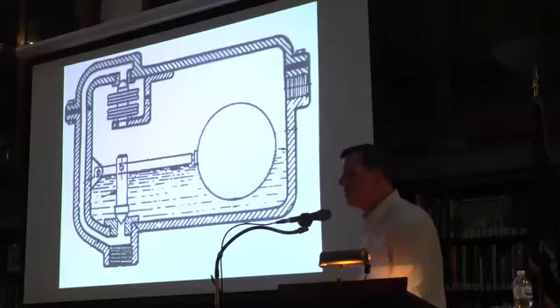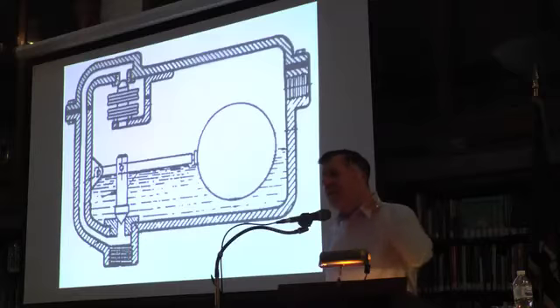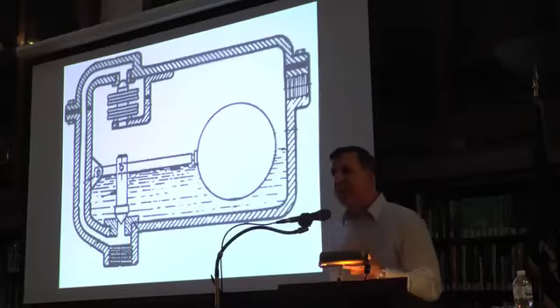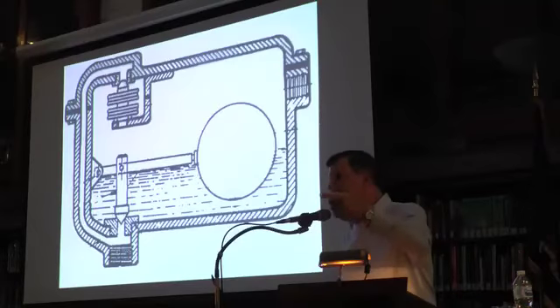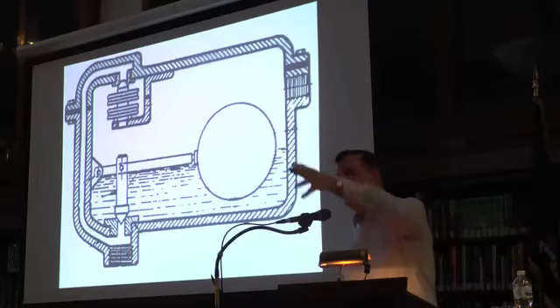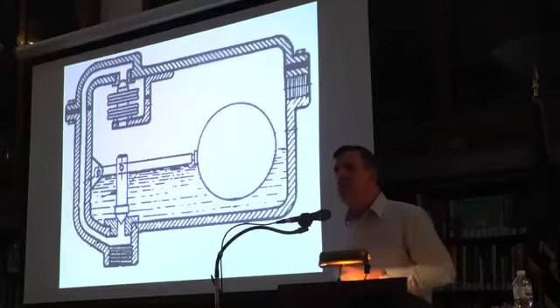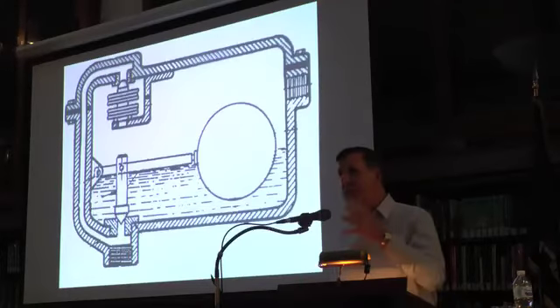But if you think about two-pipe steam, there's a steam trap on every radiator. And the only thing that floating thermostatic traps are handling is the condensate that forms in the main feeding those radiators. So you might have a trap on a line that's 300 feet long. Let's say there's a 2-inch line that goes up 300 feet in the air. The only thing that trap has to handle is the amount of condensate you're going to get by heating 300 feet of 2-inch pipe. It's not much condensate. So that would be a 3/4-inch trap.